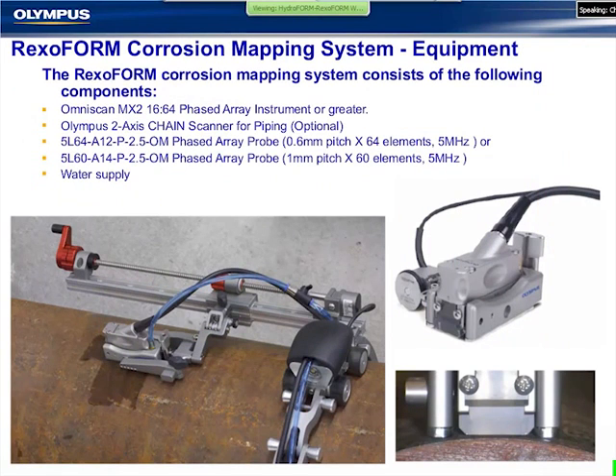And then a very similar inspection as far as the setup and the data analysis; it's all the same, but in this we use a Rexolite wedge. Now, when we were using hard Rexolite wedges just on the pipe surfaces, they either rock when they're flat or, when they're contoured, require a larger footprint and specialized water delivery couplant, and we're not nearly as efficient.